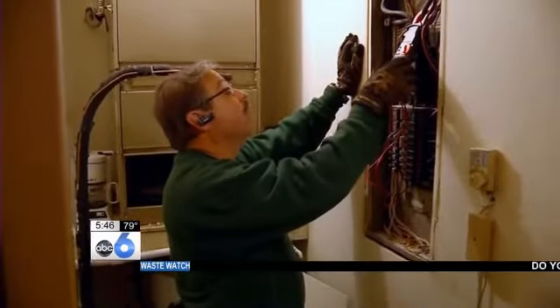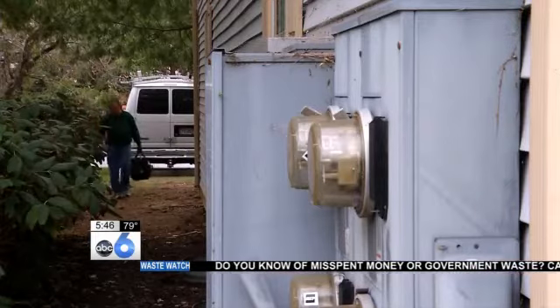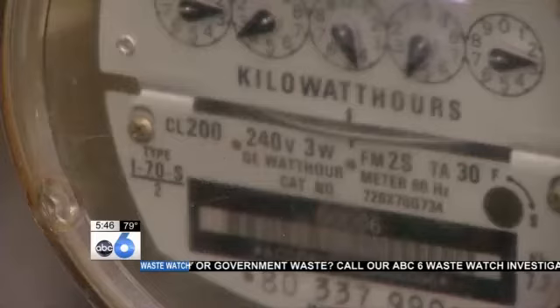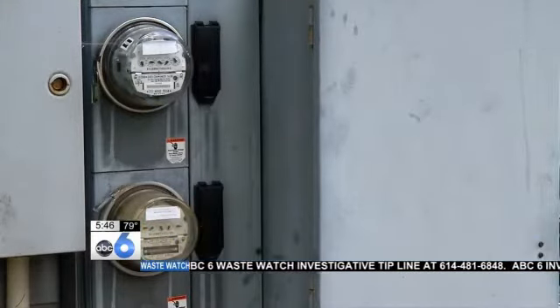That's still not a whole lot for this service. With no loose connections inside, it's back outside to look at the meter. Diehl opens the meter and checks the connections — those are tight as well. No loose connections, only a dial that's spinning fast. Personally, he thinks it's the meter. Still, AEP claims the meter is working properly.